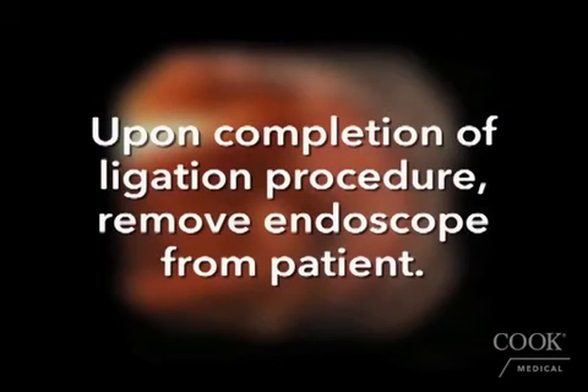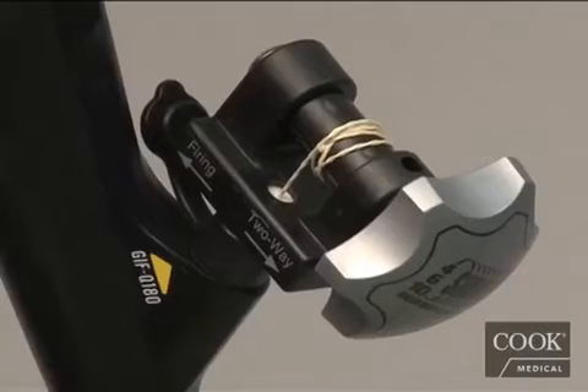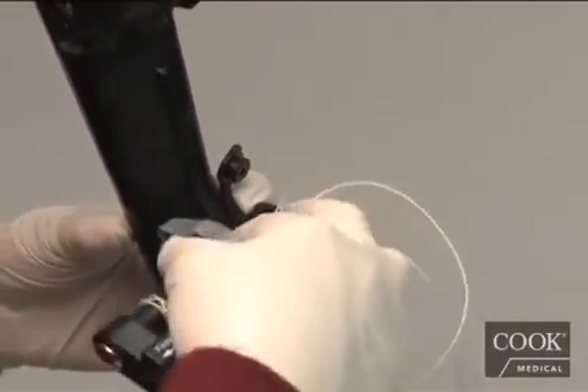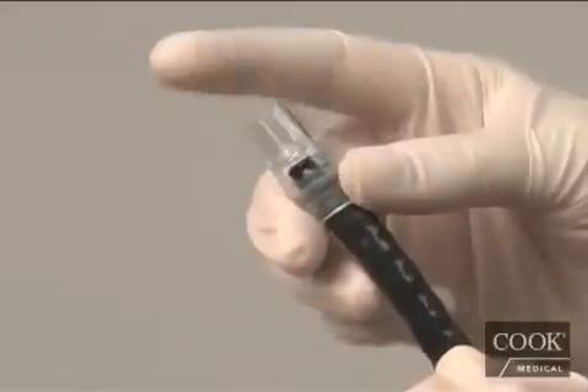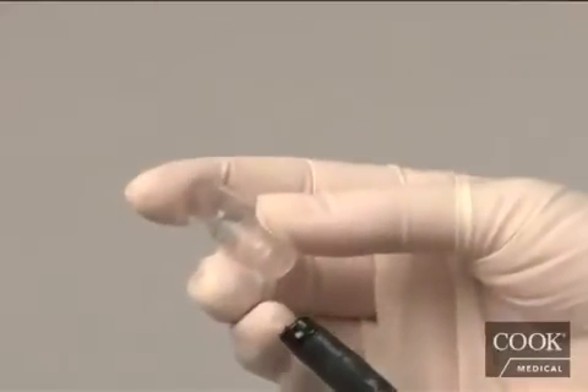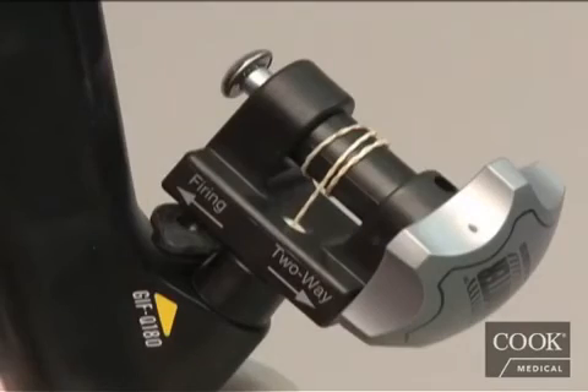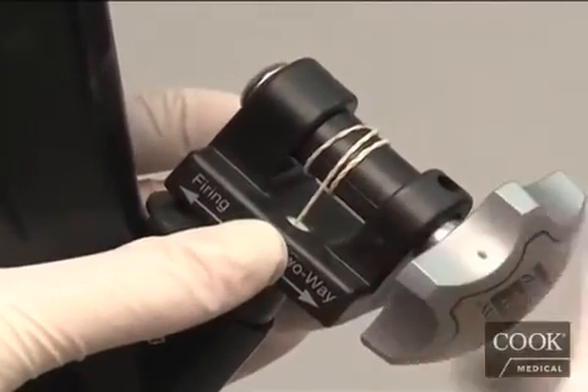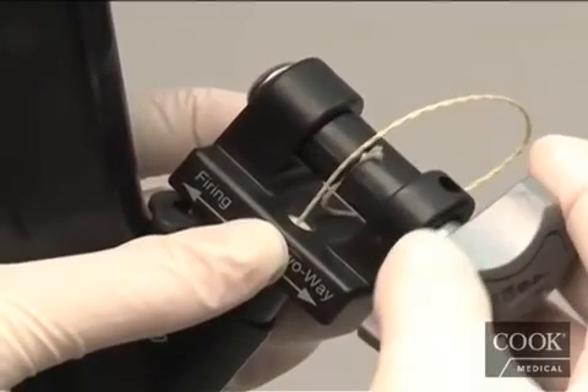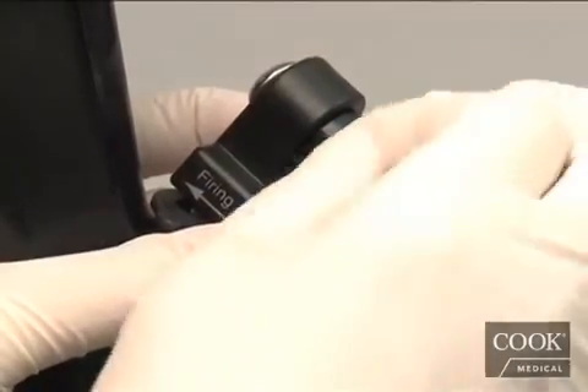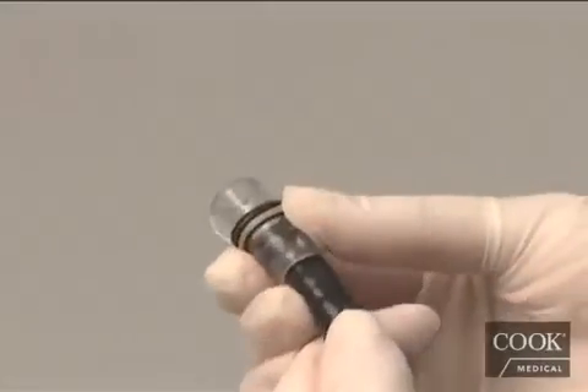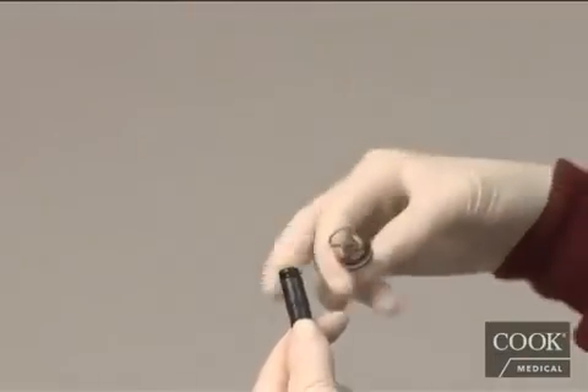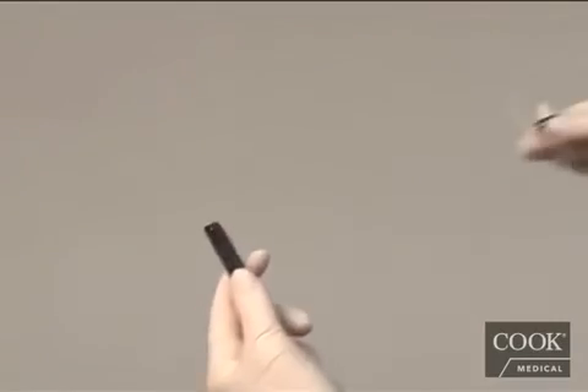Upon completion of the ligation procedure, remove the endoscope from the patient and dismantle the device as follows. If all of the bands have been fired, remove the handle and attached trigger cord from the accessory channel. Remove the barrel from the endoscope tip. If any unfired bands remain on the barrel, place the handle in the two-way position. Loosen the trigger cord from the spool, then remove the handle from the accessory channel cap. Detach the trigger cord from the handle slot, and remove the barrel from the endoscope tip. Then pull the trigger cord through the channel and out the endoscope tip.